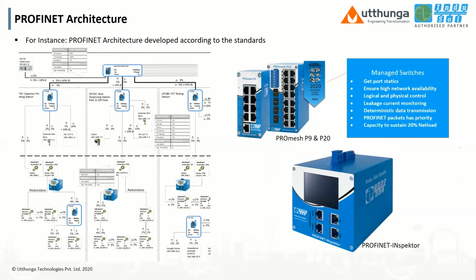So what is important in PROFINET? In Profibus, we need to do proper maintenance, proper testing, or proper monitoring. But in PROFINET, quality starts from the planning of architecture. You can see on the left side, we have developed one architecture for one of our clients with exact standards. Standards means in PROFINET, load is the main issue. If the load is not split properly, the network will go out. Network will go out means maybe if you have some conveyors, these conveyors will go for intermittent tripping, then the production line will stop. That's the main issue.